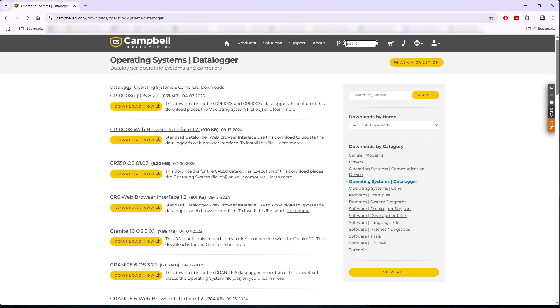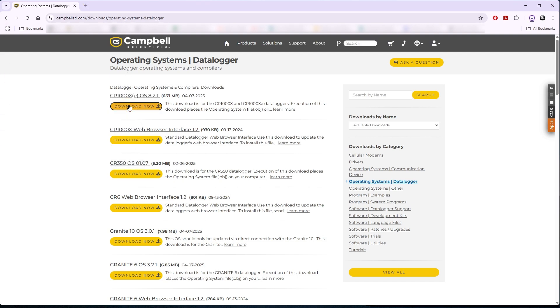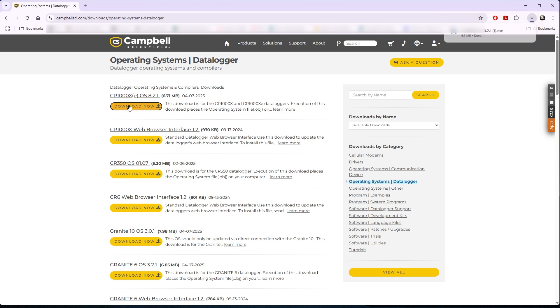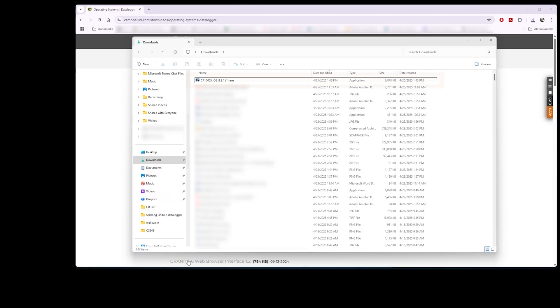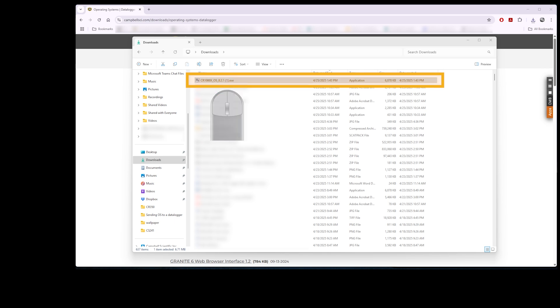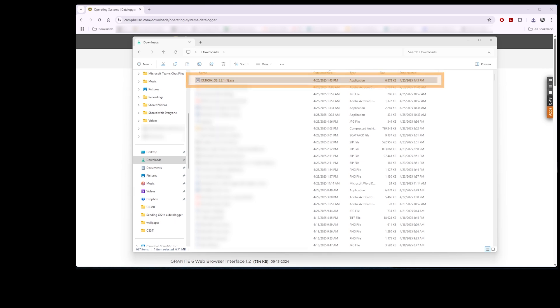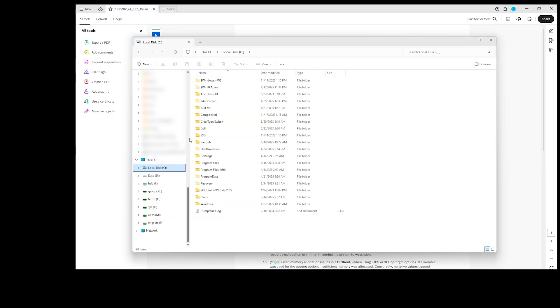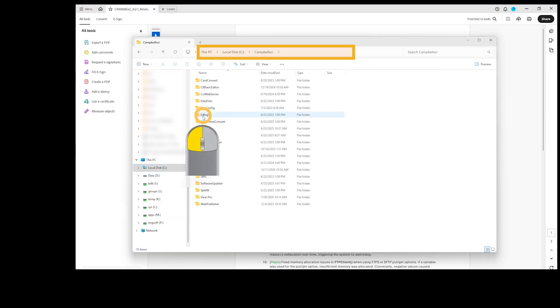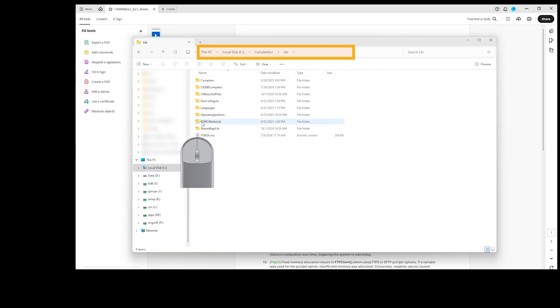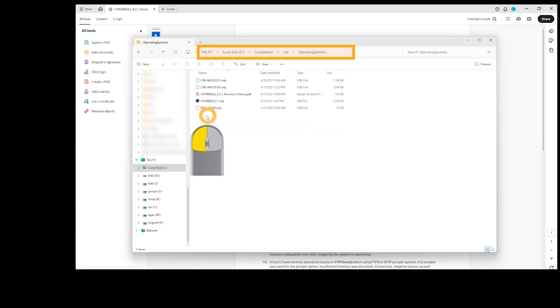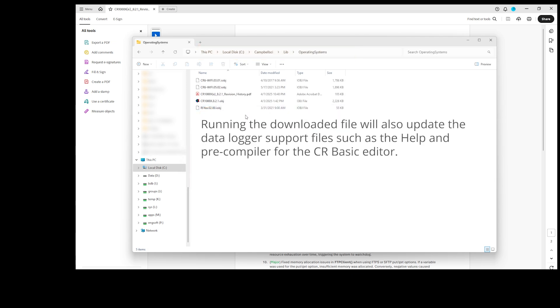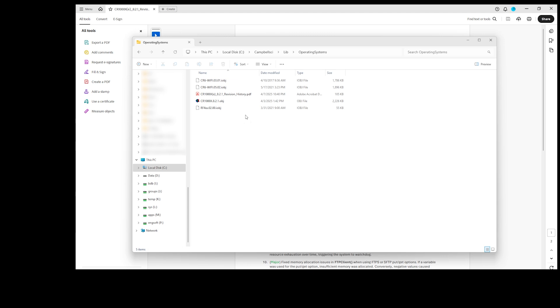Click Download Now. The executable file is downloaded to my Downloads directory. Double-click the file. This will place the OS.obj and any .iobj files in the C:\CampbellSci\Lib\OperatingSystems folder. Running the downloaded file will also update the data logger support files, such as the help and precompiler for the CRBasic Editor.